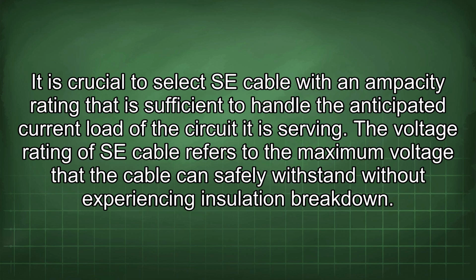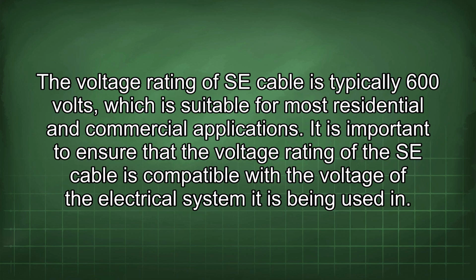The voltage rating of SE cable refers to the maximum voltage that the cable can safely withstand without experiencing insulation breakdown. The voltage rating of SE cable is typically 600 volts, which is suitable for most residential and commercial applications. It is important to ensure that the voltage rating of the SE cable is compatible with the voltage of the electrical system it is being used in.